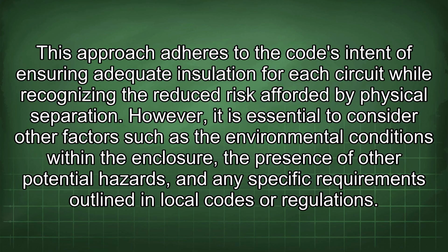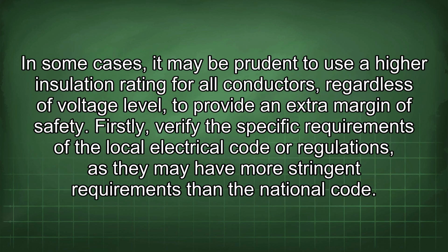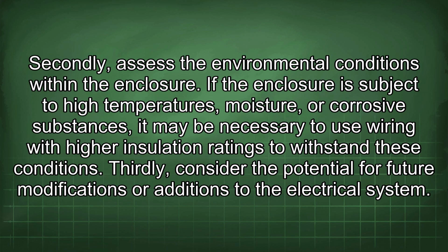However, it is essential to consider other factors such as the environmental conditions within the enclosure, the presence of other potential hazards, and any specific requirements outlined in local codes or regulations. In some cases, it may be prudent to use a higher insulation rating for all conductors, regardless of voltage level, to provide an extra margin of safety. Firstly, verify the specific requirements of the local electrical code or regulations, as they may have more stringent requirements than the national code. Secondly, assess the environmental conditions within the enclosure.